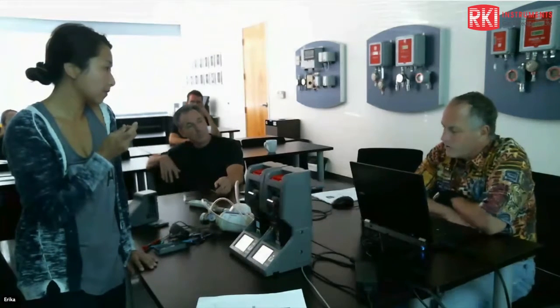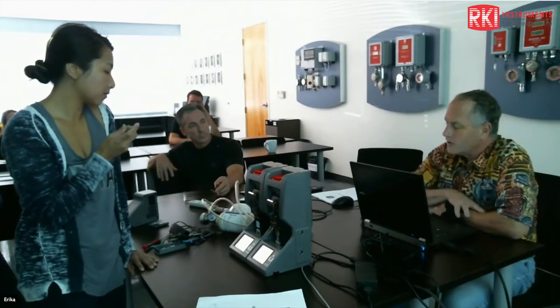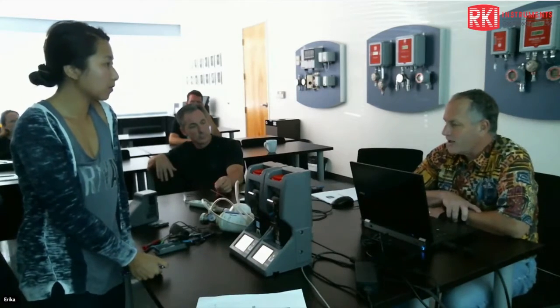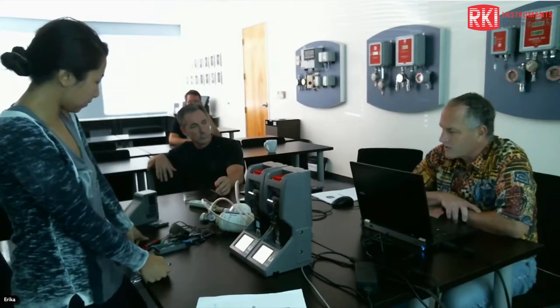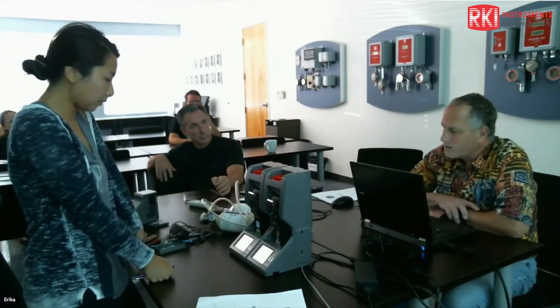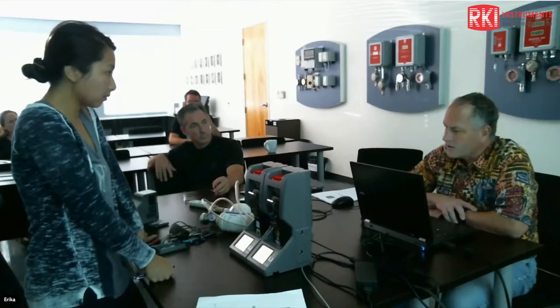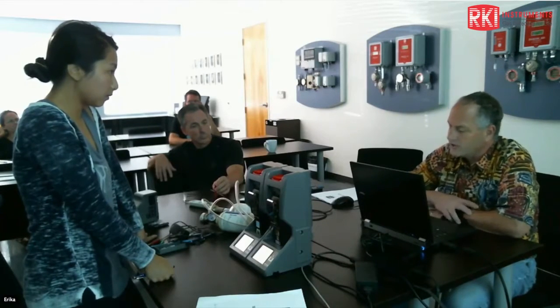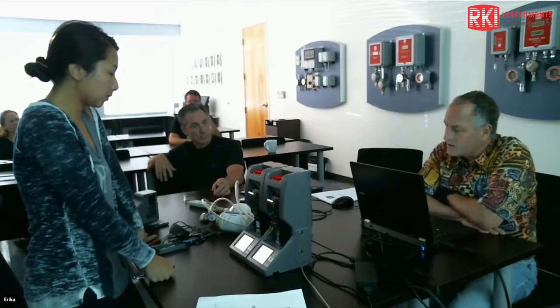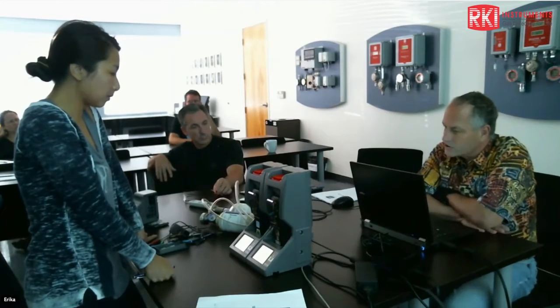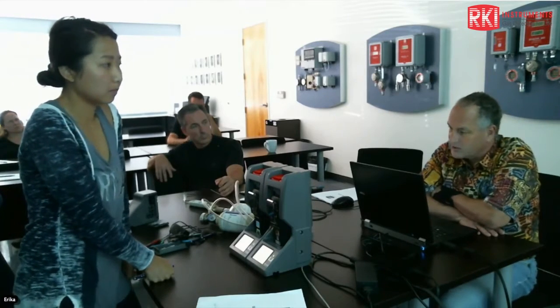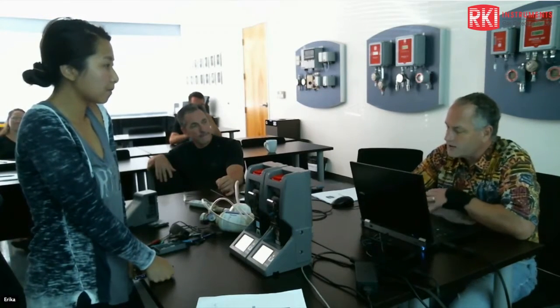It's saying that, Todd, because the 4 gas setting that you have in the instrument is the setting that tells it whether or not to reset the bump date or the cal date when you do a successful bump or a cal. But in the docking station, it still allows you to do that, but it's just telling you that you didn't do a complete bump or calibration. The inlet error means you don't have HCN selected as one of your gases. So it'll still show as a pass for the sensors that are active that did get bumped or calibrated, but it's going to tell you, just to let you know, you didn't do a complete calibration. Okay, all right. Good enough. That incomplete calibration will still reset your calibration reminder if you have it set for just 4 gas.